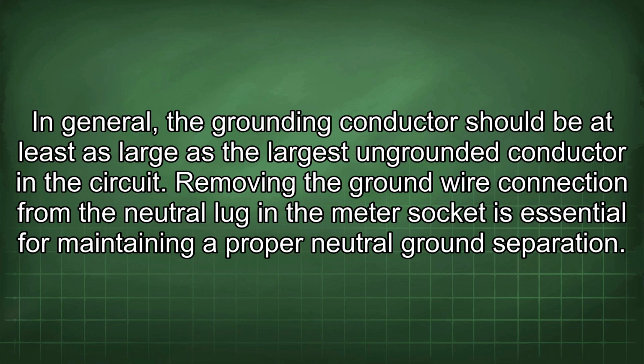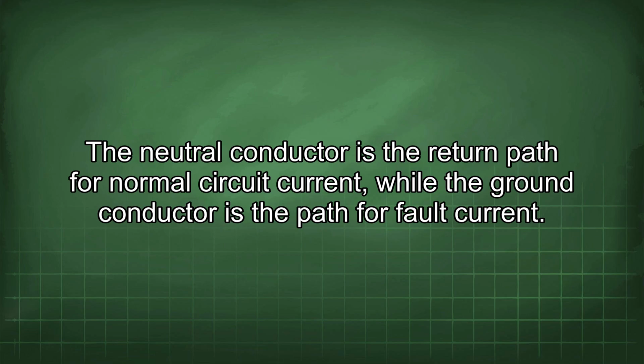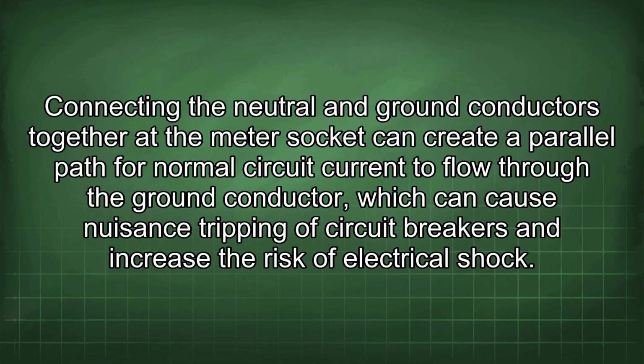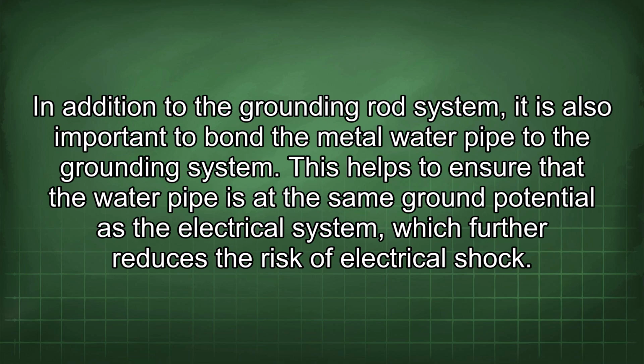Removing the ground wire connection from the neutral lug in the meter socket is essential for maintaining a proper neutral ground separation. The neutral conductor is the return path for normal circuit current, while the ground conductor is the path for fault current. Connecting the neutral and ground conductors together at the meter socket can create a parallel path for normal circuit current to flow through the ground conductor, which can cause nuisance tripping of circuit breakers and increase the risk of electrical shock. In addition to the grounding rod system, it is also important to bond the metal water pipe to the grounding system.